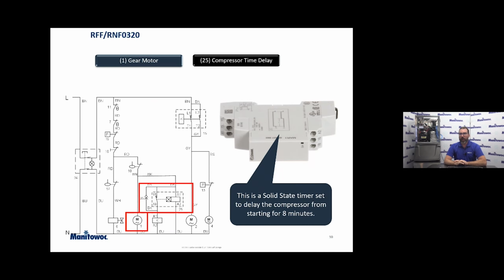Now there is a time delay bypass that I talked about. There are going to be 2 black wires with a connector that has nothing plugged into it. You can see on the wiring diagram here, it's labeled as number 35. That is a bypass. What that bypass will do, if we need to troubleshoot or something's going on, we want to make sure that compressor runs and we don't want to wait the 8 minutes. We're going to want to jump that with a paper clip, a piece of wire with 2 connectors on the end, whatever you have available. Careful, this is line voltage, so be wary of that when you're doing this.